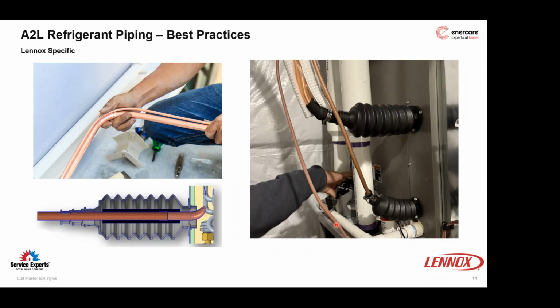They are slid over the brazed joint so that any possible leak at either joint is forced into the case portion or the ducted portion of the coil where the refrigerant sensor is located, with the hopes that it'll activate the leak mitigation measures at the refrigerant detection system, which is the control board we just looked at. You can see in the picture there's a gear clamp at the back end of the sleeve, and that's basically to seal up that sleeve around the back end of the pipe. It does come with instructions if there is some confusion or concern about how they should be installed. Like I said, that gear clamp will keep things sealed up.